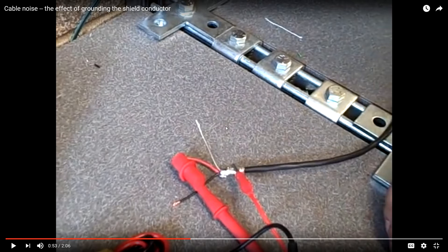When I tell you to actually terminate your shielded drain, this is the drain, and this needs to go to an earth ground in order for this cable to function as it should. You cannot just use shielded cable and expect that the shield will work without connecting the drain properly. That is why when you see shielded cables being used in a commercial environment, when you're talking about fabrication and building cables, why it is so expensive. You are talking about a lot of soldering, a lot of terminalizing each drain for both ends.